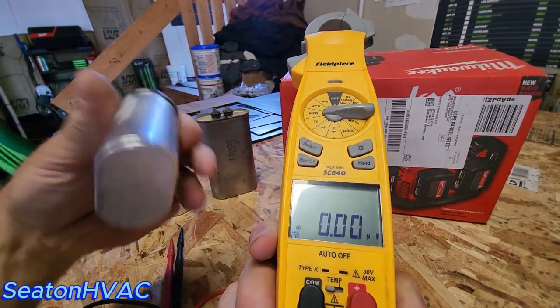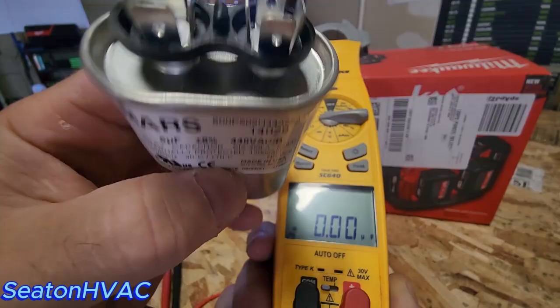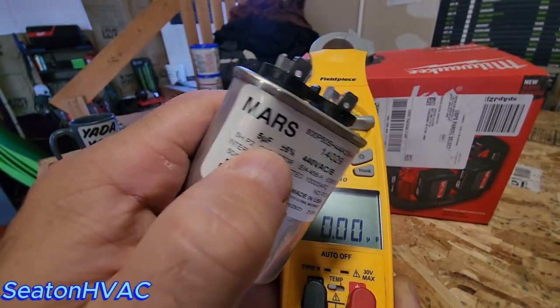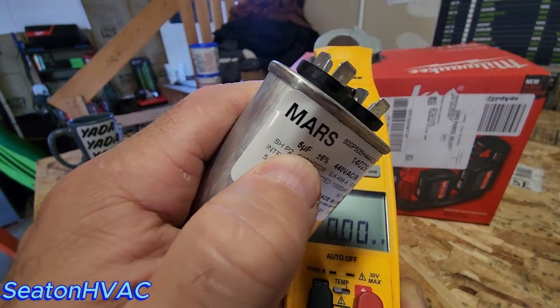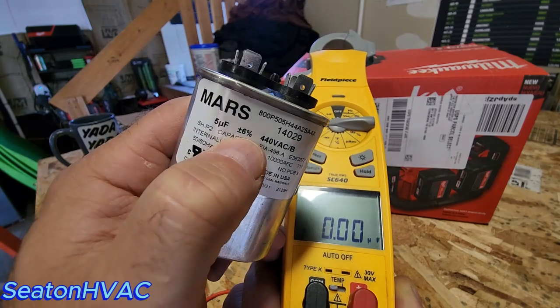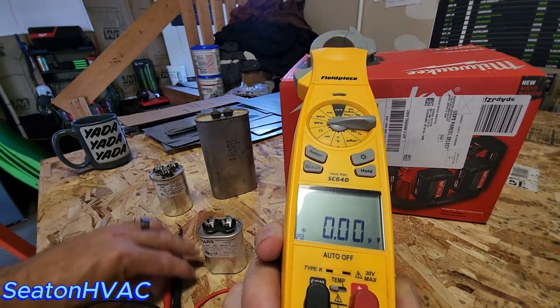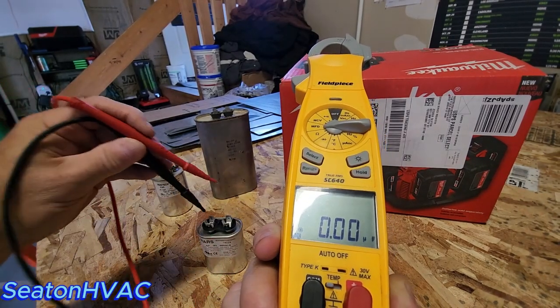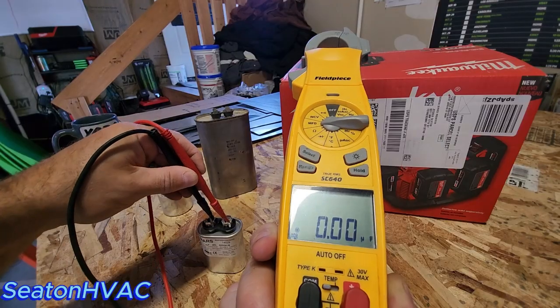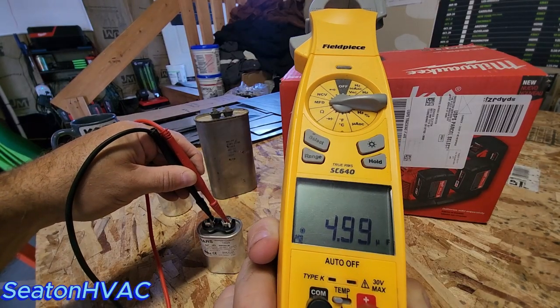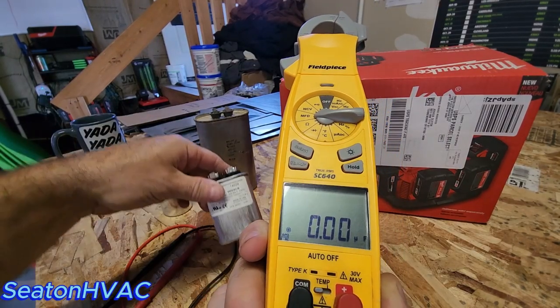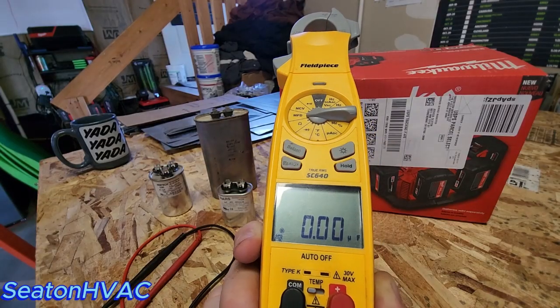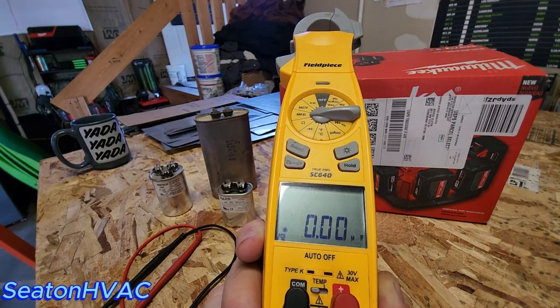And then lastly, we have our single fan run capacitor, and that'll just have one number on it, your 5 microfarads. Again, it's plus minus 6%. Let's test that out. And again, on these ones with 2 terminals, it doesn't matter what lead you put on what. And 4.99, we know that that's good. So there you are. Let's move on to the contactor.